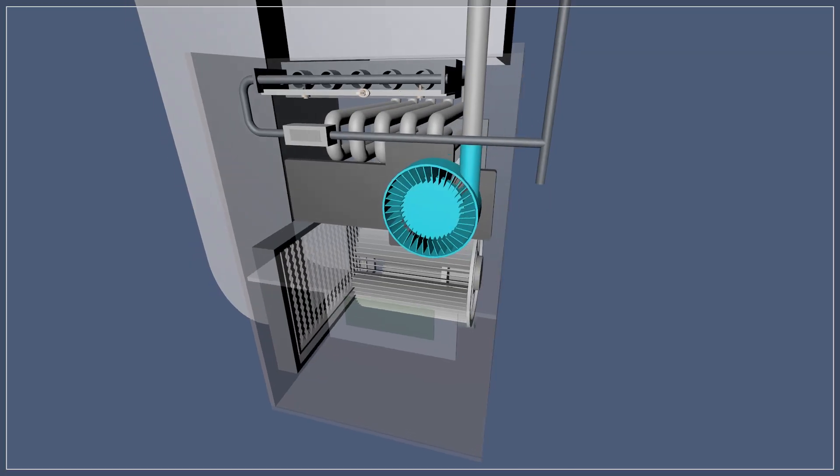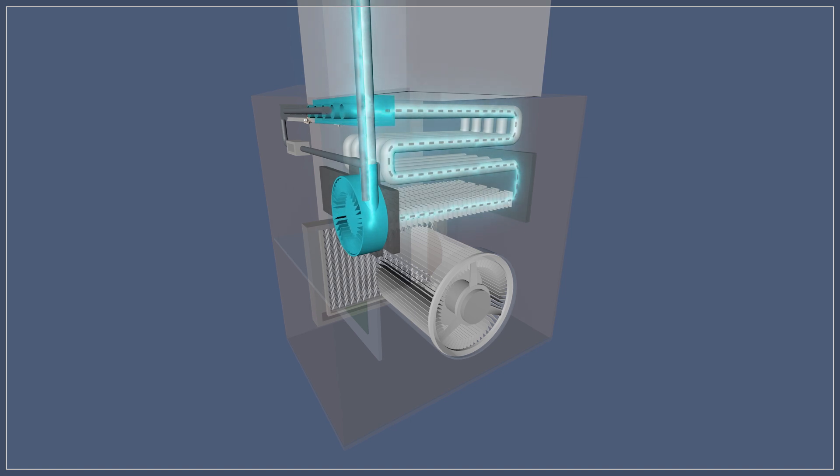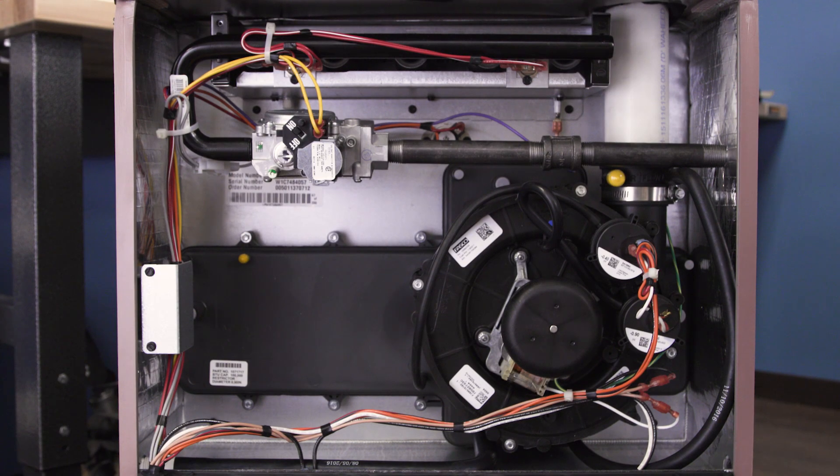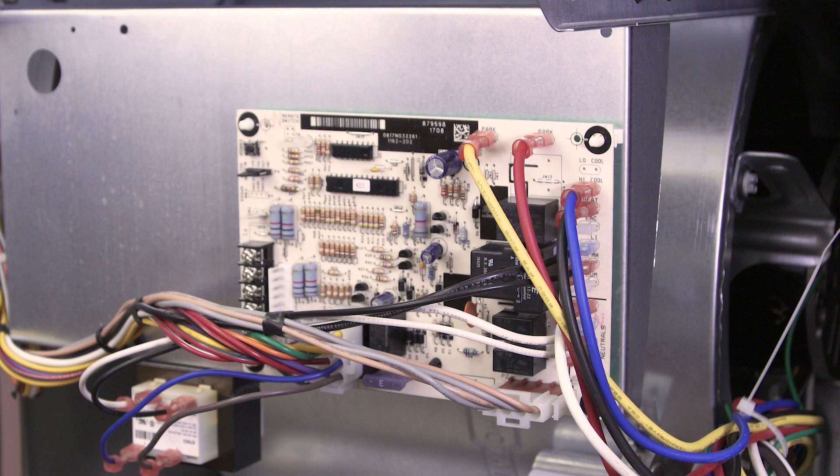If your furnace has power, then turn on the thermostat and observe the startup sequence. First, the draft inducer fan pulls air through the heat exchanger. This ensures that all fumes are exhausted during combustion. If the inducer isn't running, then the motor might be seized or burnt out. Additionally, the wires could be faulty or there could be a problem with the control board.